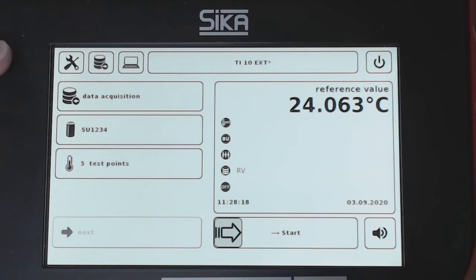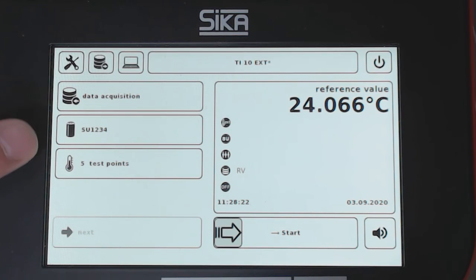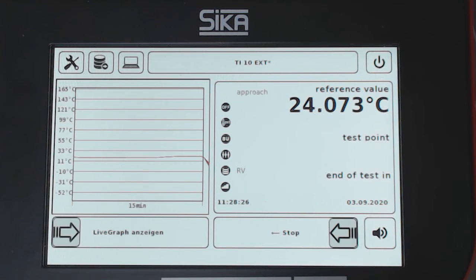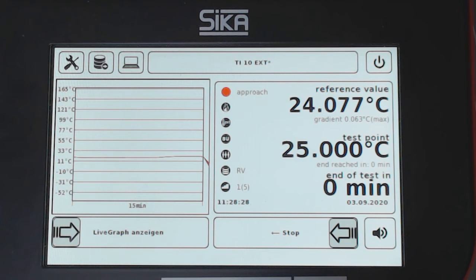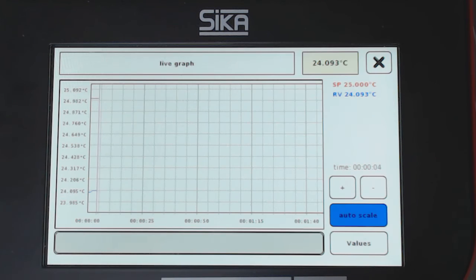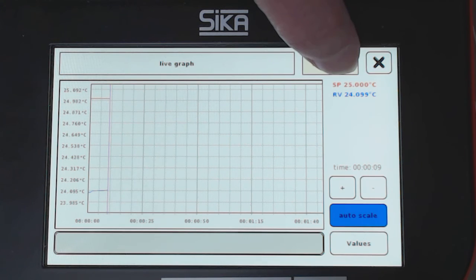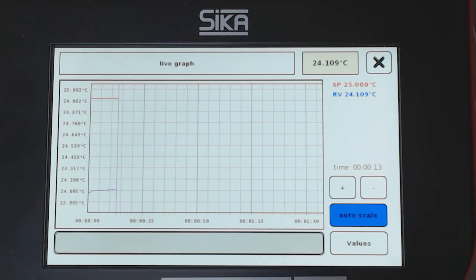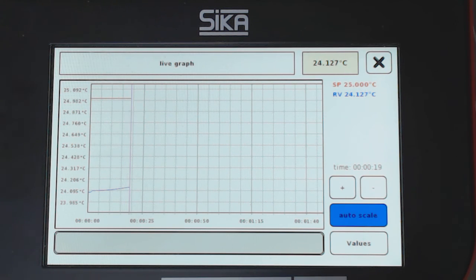I confirm. I'm complete — data acquisition, the functionality, the test points. Then I can start my test regarding the surface. I change over to live graph and I can see the curve for the set point at 25. The reference value is rising — currently 24.118 and rising.